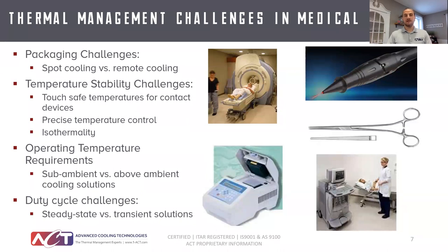There are touch-safe temperatures that we need to maintain to make sure we don't damage skin. And there are isothermality requirements for things like diagnostic equipment — making sure all the samples within a PCR machine are within the same temperature so they cycle at the same rate. The operating temperature requirements can range from really below ambient, meaning it needs refrigeration to be cooled, or above ambient cooling, which is often available for things like computer chips and CPUs.